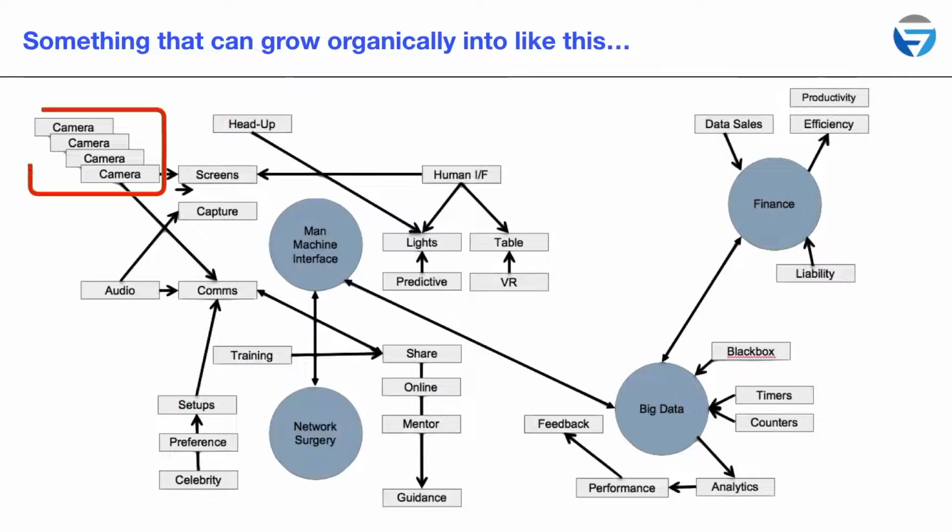So this is where we are now, pretty much. You have a number of video sources: camera, C-arm, ultrasound, endoscope. That's the normal. The camera could be the in-light camera or room camera. And then you have a number of displays, two surgical displays, maybe a big flat panel on the wall. And you have a human interface, normally a video touch panel. So you just press a few buttons and you do your routing. That's controlled by a machine, which is called your man-machine interface controller and the routing controller. And that's every system for the last 20-odd years, pretty much.